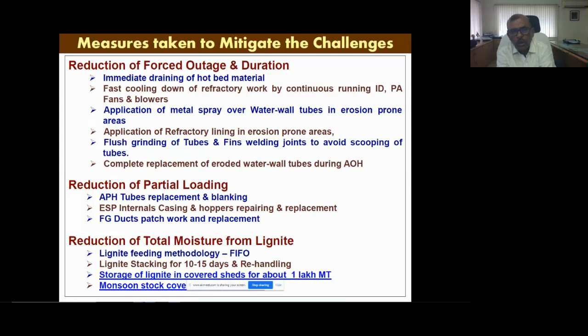As there is a lot of erosion, we have gone for metal spray coatings in the corners and the high erosion areas. In the roof tube, we have gone for arc spray. Then in the corner areas where we have provided refractory lining, we are providing additional refractory lining where we find more erosion causing frequent boiler tube leakage and forced outage. Since the bed materials, or the heat transfer materials, slide on the combustor walls, we have to have a flush finish on the joints, and this also takes a lot of time and needs due care. Then only can you avoid boiler outages. And then there is complete replacement of the water wall tubes and other vulnerable areas where thickness has gone below 30-40% of the original thickness, to avoid forced outage during running of the machine and the boiler.